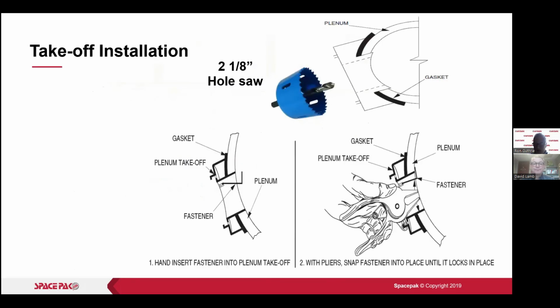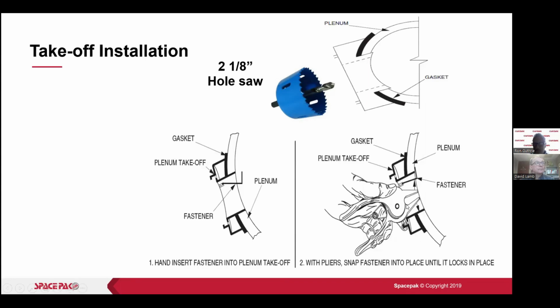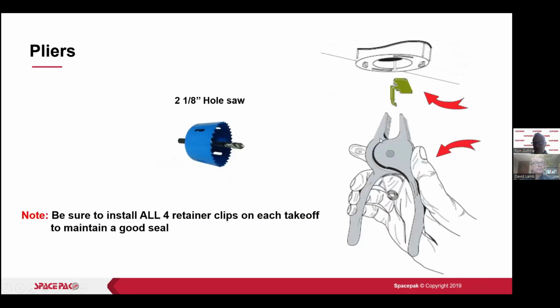The takeoffs go into the plenum using a 2 1/8-inch hole saw. This is a pair of reverse acting pliers, and this is available. These make the installation of the clips that come in the kits a lot easier. So there's a gasket that goes in here, and there's a gasket that goes in here, and the outlet seals against that gasket and provides a sealed connection for the quarter turn quick connect fitting that we use. So you'll see that fitting right there. That's quarter turn, gasket in between. Get the pliers, your hands will thank you at the end of the day, and get a 2 1/8-inch hole saw, which is what you'd use to install these.